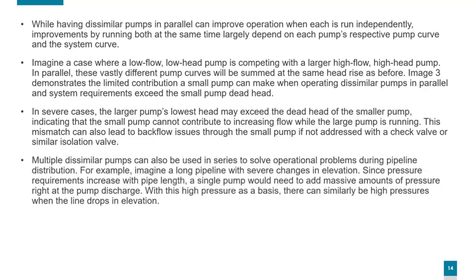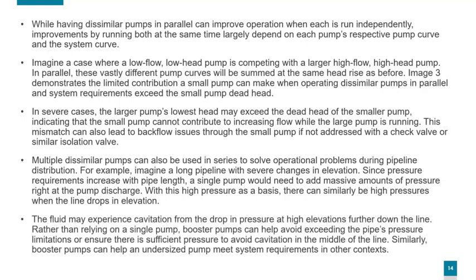Multiple dissimilar pumps can also be used in series to solve operational problems during pipeline distribution. For example, imagine a long pipeline with severe changes in elevation. Since pressure requirements increase with pipe length, a single pump would need to add a massive amount of pressure right at the pump discharge. With this high pressure as a basis, there can similarly be high pressure when the line drops in elevation. The fluid may experience cavitation from the drop in pressure at high elevations further down the line.